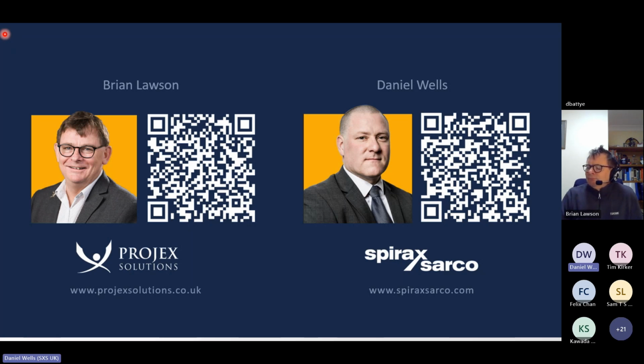If you've got flooding in the infrastructure, what we generally find is it's easy for an expert to diagnose when a steam trap has failed closed and resulted in that flooding. It's not so easy for the site owners to demonstrate that, but they're more likely to get issues creeping up over time. So they're the mechanical issues, such as the erosion, the corrosion, the water hammer. We're more likely also to find that the energy content of the steam degrades and deteriorates. These are things that are not as immediate as identifying when the condensate can't get away from a process.